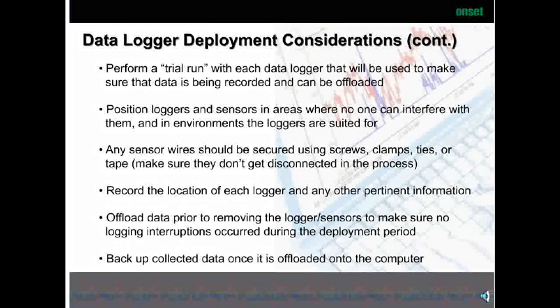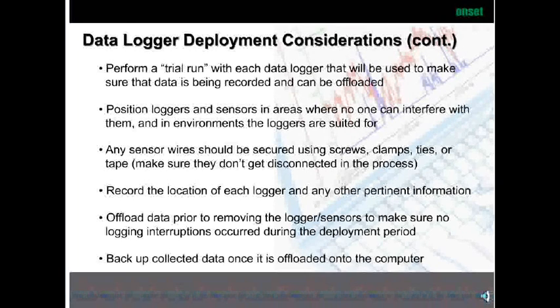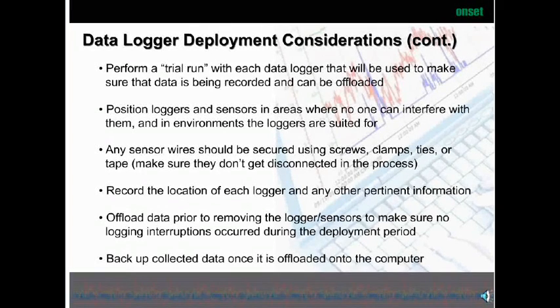Record the location of each logger and any other pertinent information. If you do a lot of logging and have a lot of equipment, sometimes it gets lost and forgotten, so make sure you have a record of where that logging equipment is. Offload the data prior to removing the logger or sensors to make sure no logging interruptions occurred during the deployment period — if you don't do that, you can lose the data, and it's tough when you spend all that time and effort. Make sure you back up the collected data once it's offloaded onto the computer. From experience, if you don't back it up, eventually you will lose it, and it's pretty valuable information.